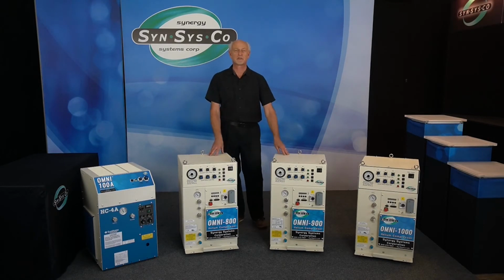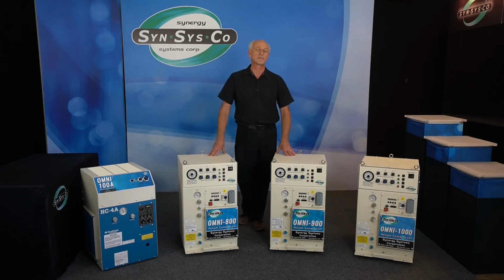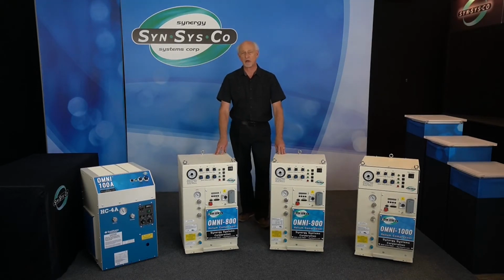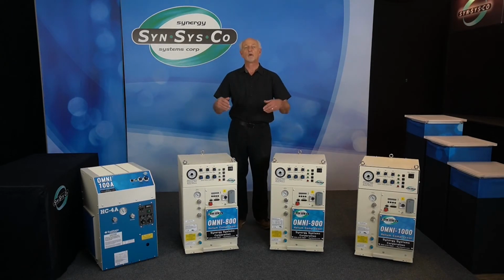So when SynSysCo discovered this, we realized there was a great opportunity in the market, and we set out to develop the OMNI module. The OMNI module creates the proper phasing, control, and voltages to run the existing installed base of many manufacturers' cryopumps. So the OMNI compressor can be installed and run the existing installed base.